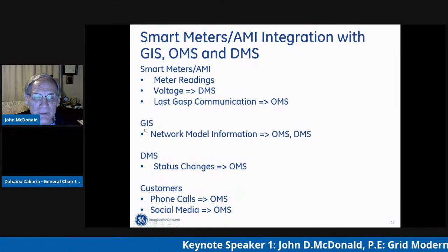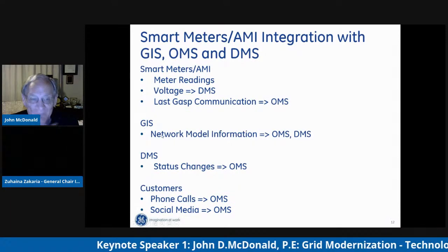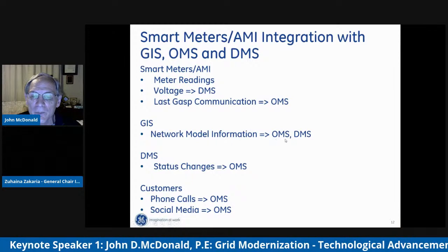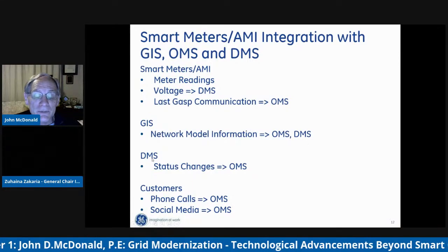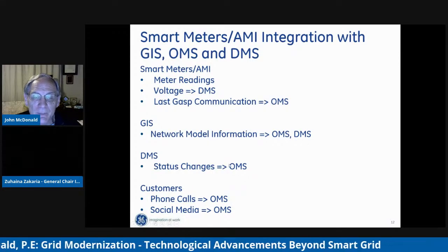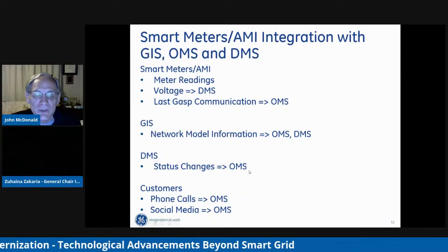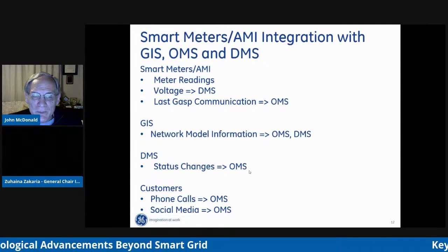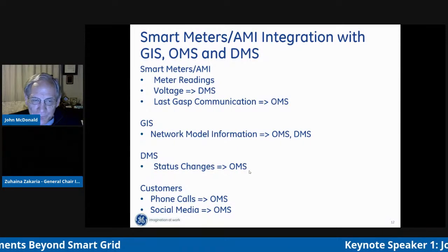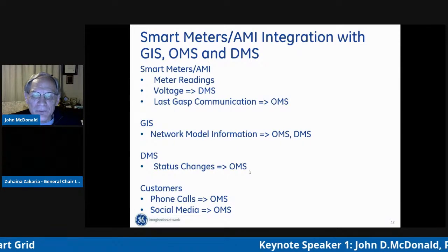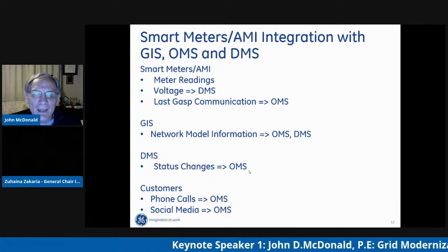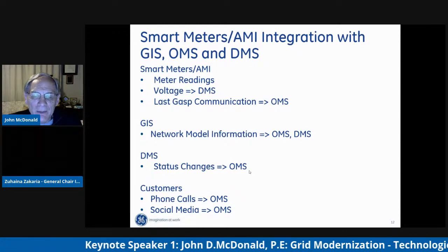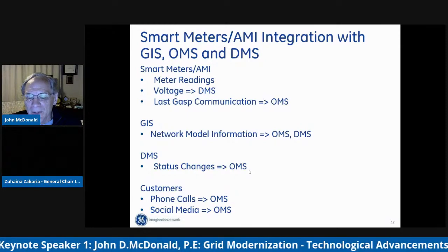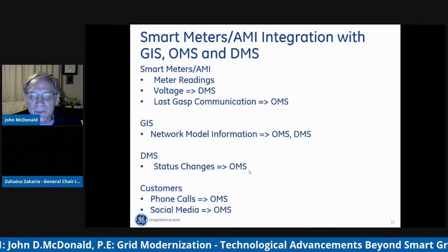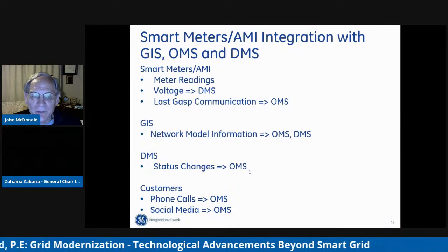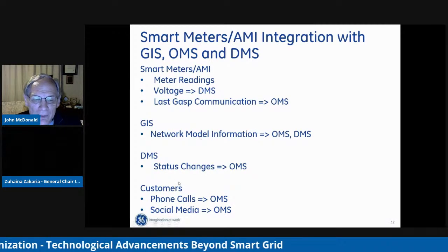The geographic information system is the reference system for the network model information for the OMS and the DMS. We also take status changes from the DMS and bring those into the outage management system. The outage management system has a network model, and if it knows a certain feeder breaker has tripped, because it has the network model, it knows all the customers connected to that feeder, and it knows now that all those customers have an outage. Very important information.